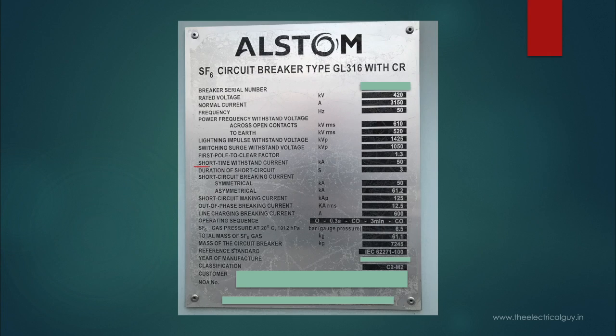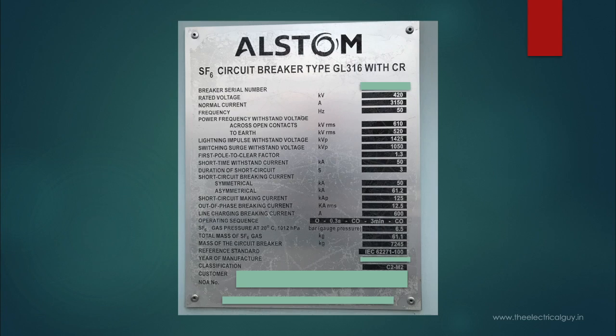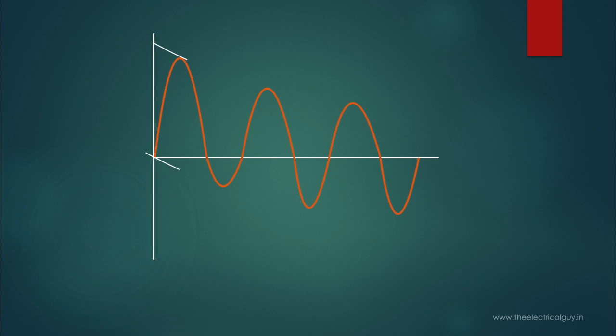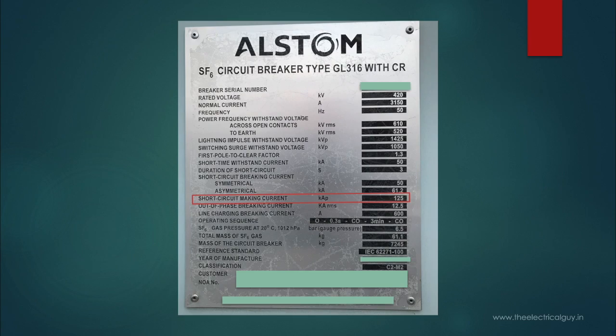Rated duration of short circuit is the time in seconds for which the circuit breaker can withstand the short circuit current — as per standard it can be 3 seconds or 1 second. Rated peak withstand current, or rated making current: if the circuit breaker closes during an existing fault, current may increase to a very high value during the first cycle, and the breaker must withstand this current and the mechanical forces it causes. It is generally 2.5 times the rated short circuit current, given in kiloampere peak. So 2.5 × 50 kA gives 125 kA making current.